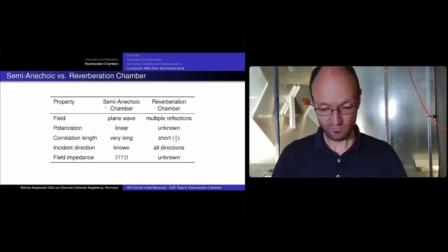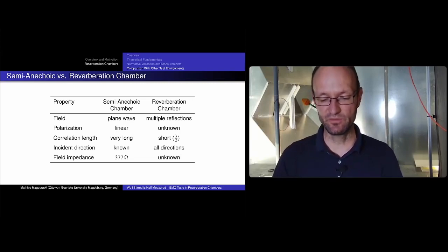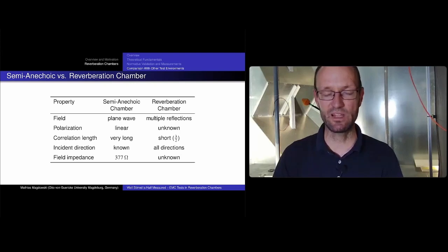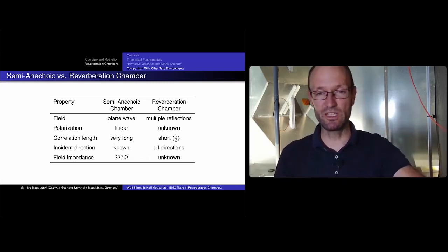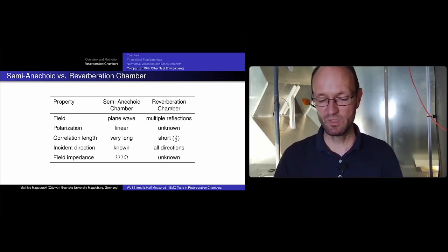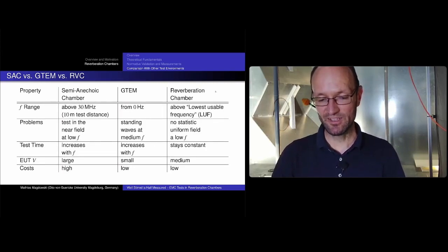In comparison: in the semi-anechoic chamber you have a plane wave field, linear polarization, a long correlation length, a known incident direction, and a well-defined field impedance of 377 Ω. In the reverberation chamber you have many reflections, unknown polarization, a very short correlation length of about half a wavelength, field arriving from all directions simultaneously, and a field impedance whose average or median is known but which varies widely at any given position.